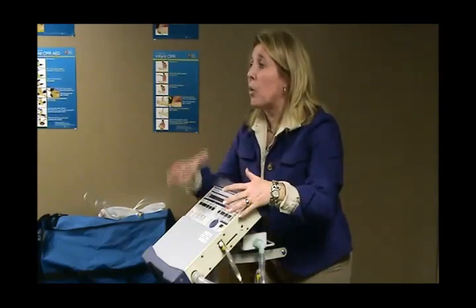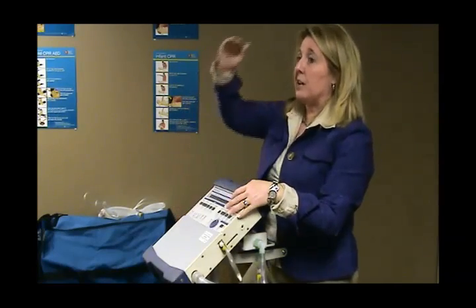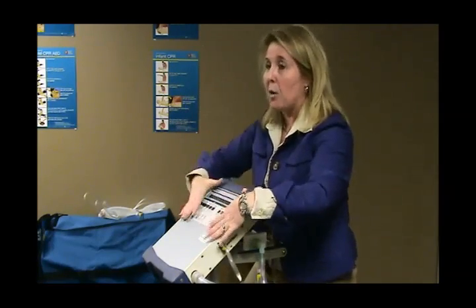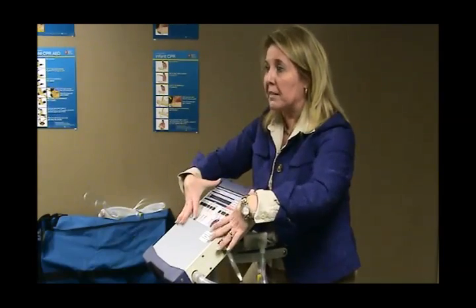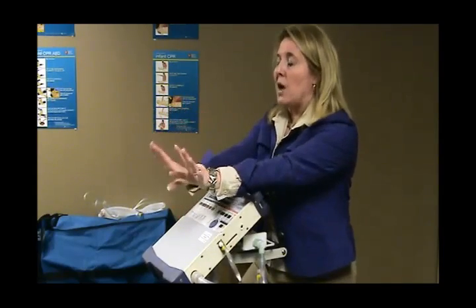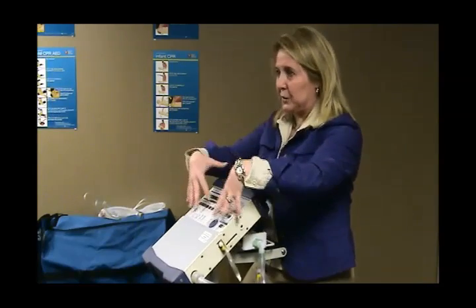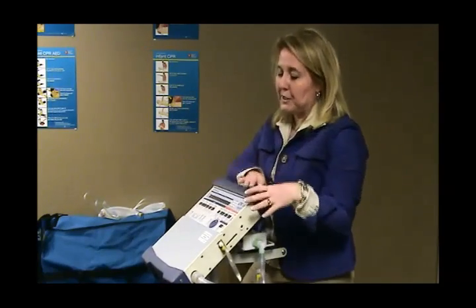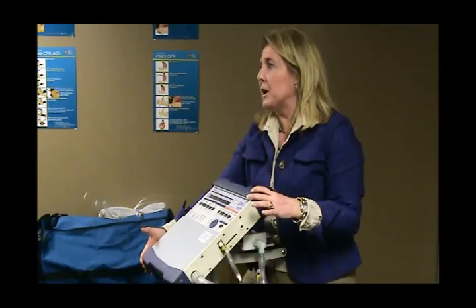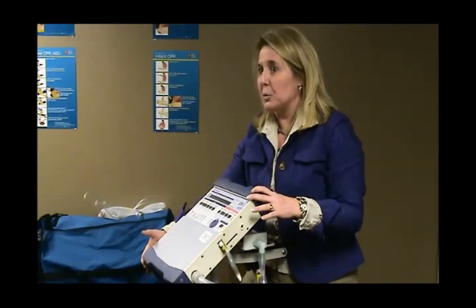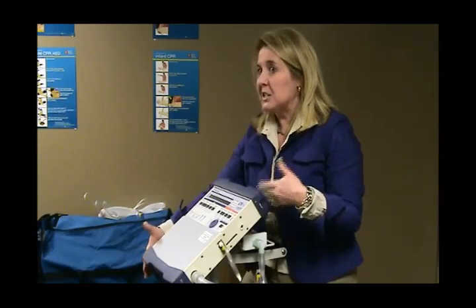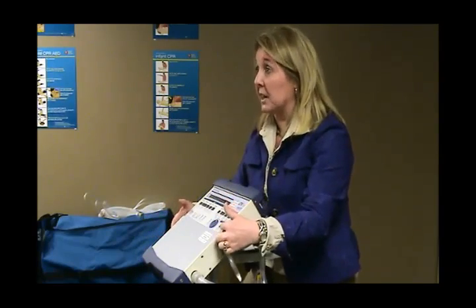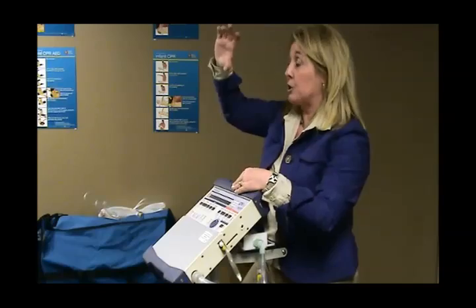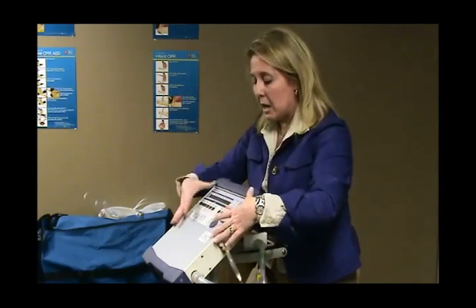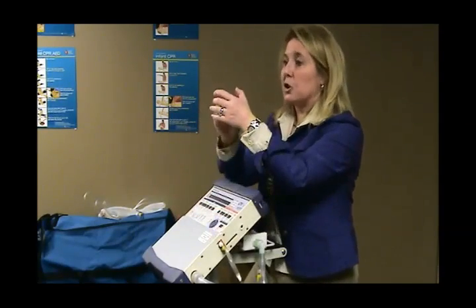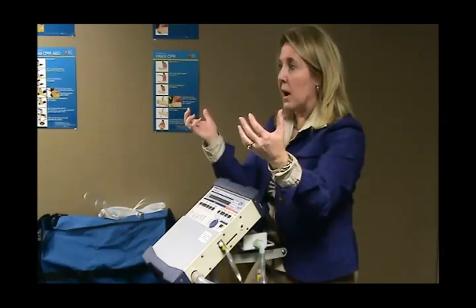So, when we are pressure ventilating somebody, we are giving them a certain amount of pressure, and again, I'm going to fall back to our newer ventilators. Let me say one thing since we're on the topic of old LTVs versus new LTVs. The first thing that you'll notice is the new LTVs are purple. So usually when you come into a room and you glance across the room at the ventilator, if it's purple, it usually has a place to dial PEEP into the ventilator. It is PEEP compensated, means the pressure is on top of PEEP, okay? So you'll notice that right away. The external PEEP valve is the other big giveaway, okay?